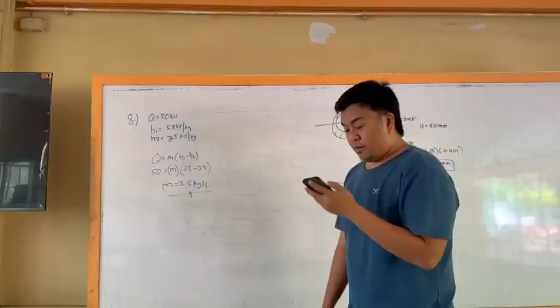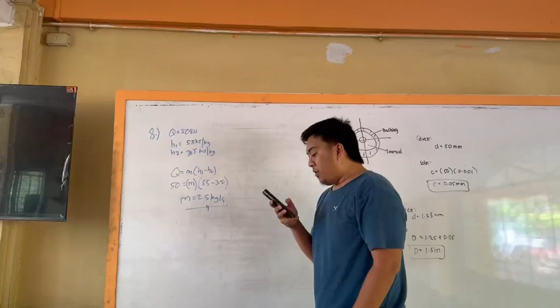For the last problem, a server room generates a total cooling load of 50 kilowatts. Air is supplied to the room at an enthalpy of 35 kilojoules per kilogram, then absorbs heat and returns to the unit at H1, which is 55 kilojoules per kilogram. The requirement here is to find the mass.